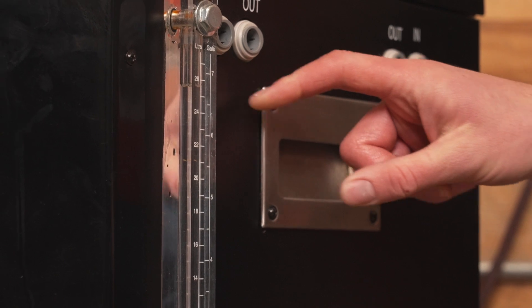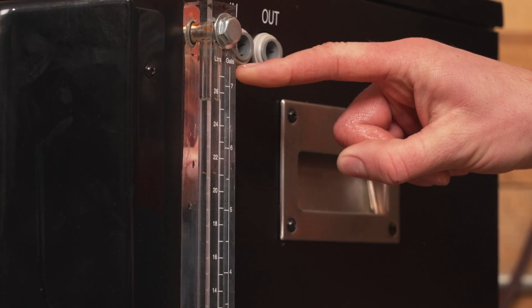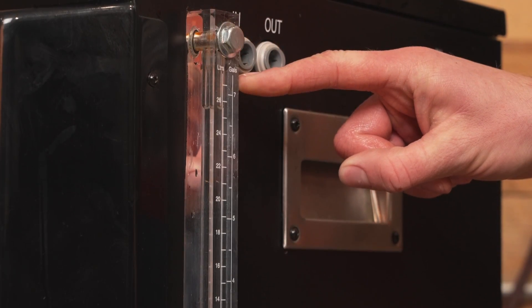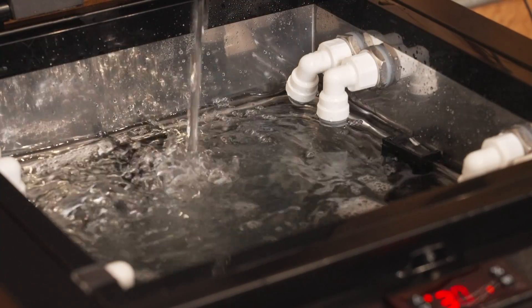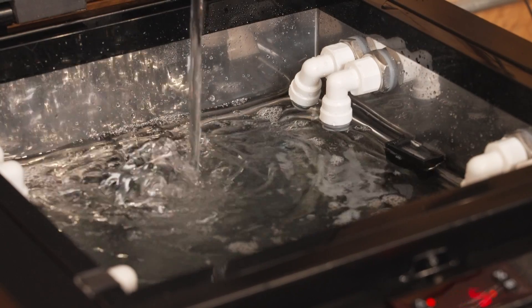Use the sight glass to monitor the glycol level. You may notice a slight decrease over time. If the level in the chiller drops below the optimal level, add more glycol to bring the reservoir up to the minimum of six gallons.